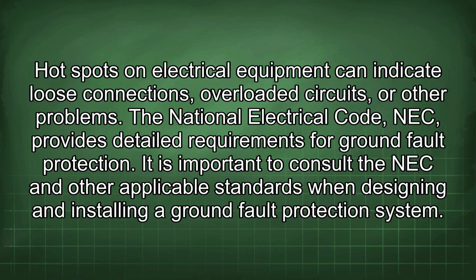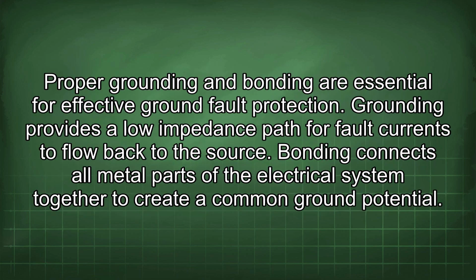The National Electrical Code, NEC, provides detailed requirements for ground fault protection. It is important to consult the NEC and other applicable standards when designing and installing a ground fault protection system. Proper grounding and bonding are essential for effective ground fault protection. Grounding provides a lower impedance path for fault currents to flow back to the source. Bonding connects all metal parts of the electrical system together to create a common ground potential.